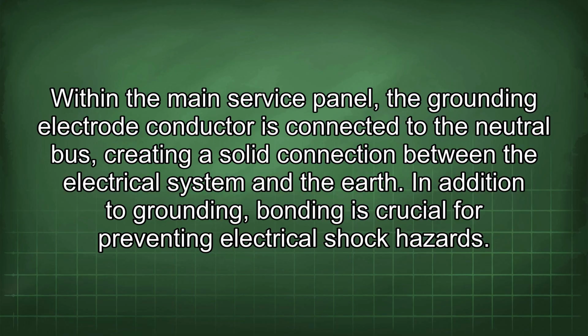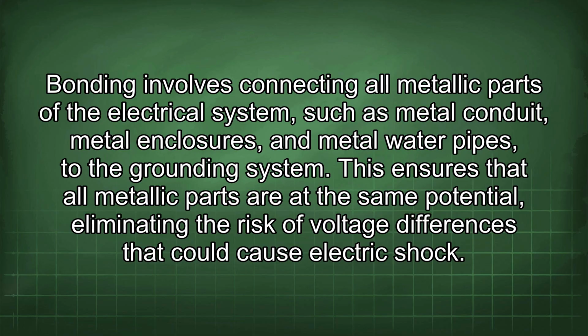In addition to grounding, bonding is crucial for preventing electrical shock hazards. Bonding involves connecting all metallic parts of the electrical system, such as metal conduit, metal enclosures, and metal water pipes, to the grounding system. This ensures that all metallic parts are at the same potential, eliminating the risk of voltage differences that could cause electric shock.